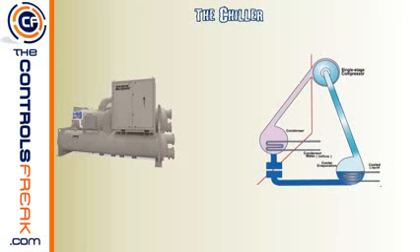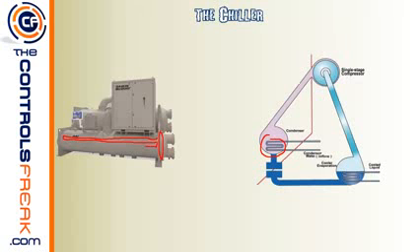The evaporator water lines run through the coils inside the air handler units, essentially the air conditioning units inside the building. One other thing to note about chillers: inside these barrels there are many bolts that seal up the two ends. Inside the barrel, the water lines are actually long tubes that run the full length of the barrels. Some chiller barrels have literally a hundred or more of these tiny tubes inside.